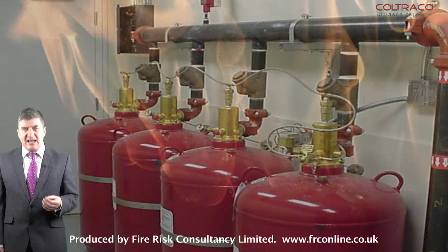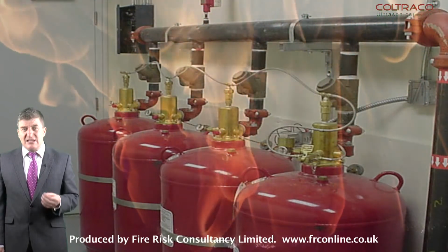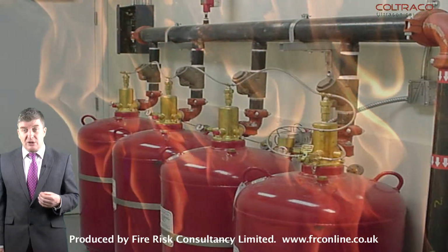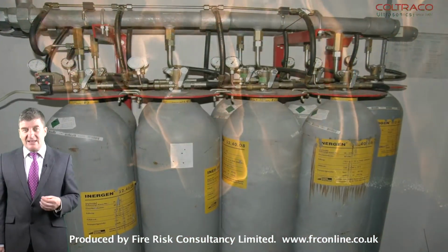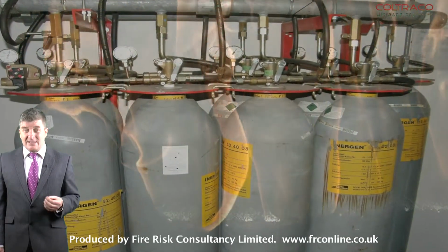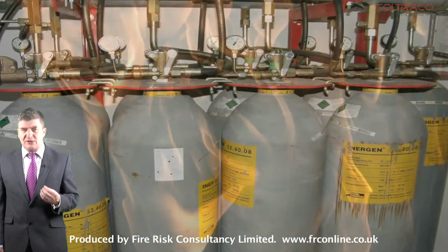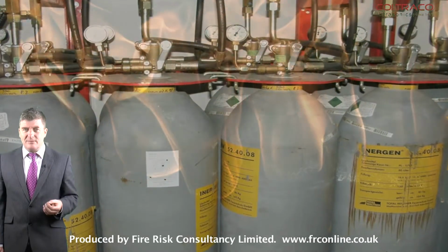Liquefied gas is a gas or gas mixture, normally a halocarbon, which is liquid at the container pressurization level at room temperature, which is normally 20 degrees C. And a non-liquefied gas is a gas or a gas mixture, normally an inert gas, which under service pressure and permissible service temperature conditions is always present in the gaseous form.